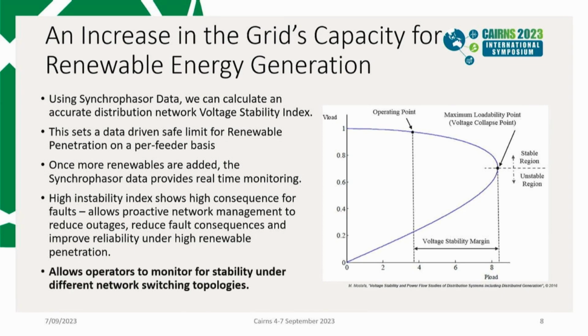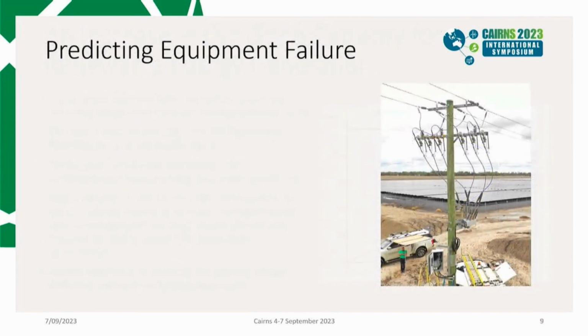And so ultimately, it allows your operators to monitor for that stability under different network switching topologies too. So if you have more than simple radial feeders, when you connect the network in different ways, this will affect the loadability of those feeders. And accordingly, when you then measure the synchrophasor data, you can get a better indication for what that maximum loadability point is. Another outcome that we saw was the ability to predict equipment failure.